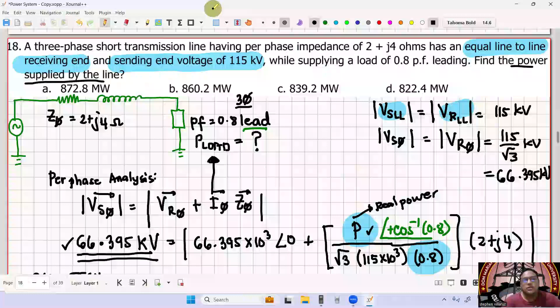Mode 2 tayo. So that is absolute value ng 66.395 kilo plus the quantity P all over square root of 3 times 115 kilo times 0.8 bar angle arc cosine ng 0.8, multiplied by 2 plus 4i.